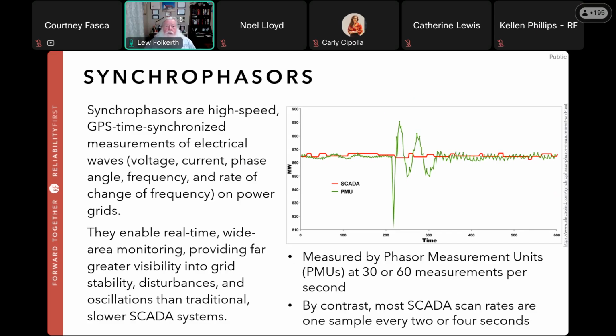You're used to normally sampling transmission or generation data on a 2 or 4 second basis for SCADA. Synchrophasors sample it much faster. Synchrophasors are actually the measurements, and they are accurate measurements and very precisely time-stamped using GPS traceable time signatures. As opposed to 2 to 4 seconds per sample, you typically have either 30 or 60 samples per second. So much faster. Therefore, you get a much better picture of what's going on the grid.